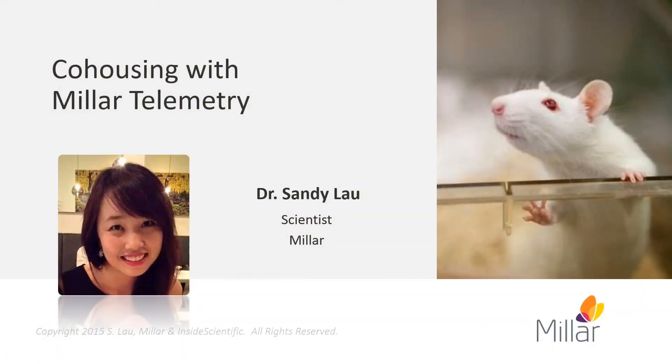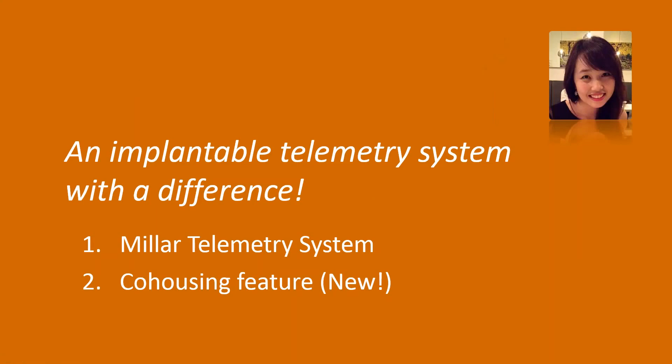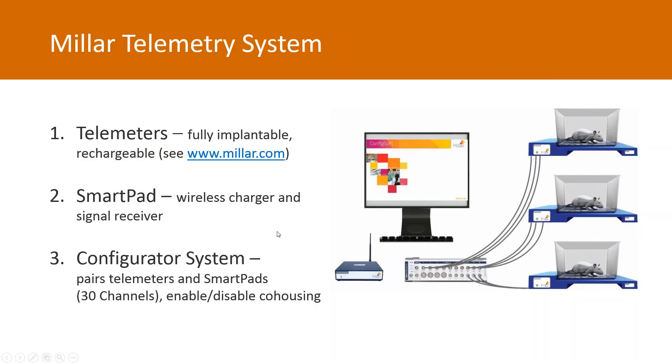Thank you, Martin. My name is Sandy and I'm a staff scientist at Millar. Today I'm going to briefly provide some background on the technology used by speakers in this webinar. I'm going to touch on some components of the Millar system, how it works, and introduce our new cohousing feature. The Millar telemetry system has three components: reusable telemeters with rechargeable batteries, smart pads, and the configurator system.